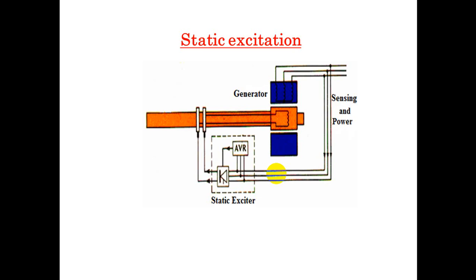Now, what are the main roles of the excitation system? 1. Adjust the excitation current according to the change of generator load to maintain the terminal voltage at a given value. 2. Control the reactive power distribution in parallel operation between generators. 3. Improve the static stability of the parallel operation of the generator. 4. Improve the transient stability of the parallel operation of the generator.